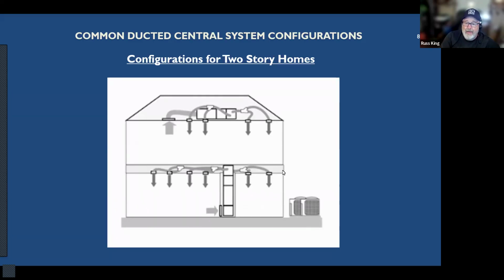And how is this happening? Okay. That can be a real challenge. And that's typically why ducts get undersized, is because there's just not enough room to fit them. The architect and the structural engineer didn't coordinate with the HVAC designer, where the HVAC designer said, "Yeah, man, I need 10-inch ducts going this way. I need 8-inch ducts going over there. I need 9-inch ducts going this way." And they get out there and like, "Oh, heck, only 7-inch ducts are going to fit." And then they end up putting in 7-inch ducts, and that's not a good thing.